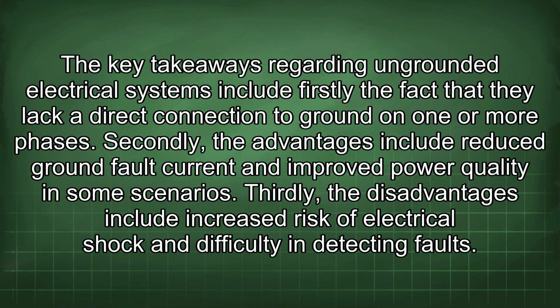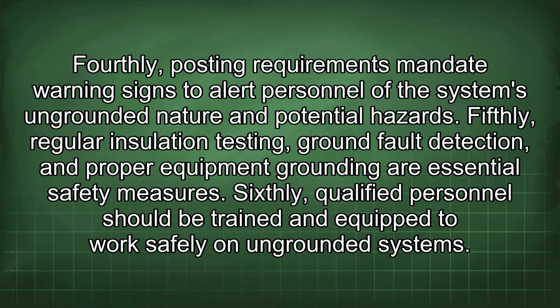The key takeaways regarding ungrounded electrical systems include, firstly, the fact that they lack a direct connection to ground on one or more phases. Secondly, the advantages include reduced ground fault current and improved power quality in some scenarios. Thirdly, the disadvantages include increased risk of electrical shock and difficulty in detecting faults. Fourthly, posting requirements mandate warning signs to alert personnel of the system's ungrounded nature and potential hazards. Fifthly, regular insulation testing, ground fault detection, and proper equipment grounding are essential safety measures. Sixthly, qualified personnel should be trained and equipped to work safely on ungrounded systems.